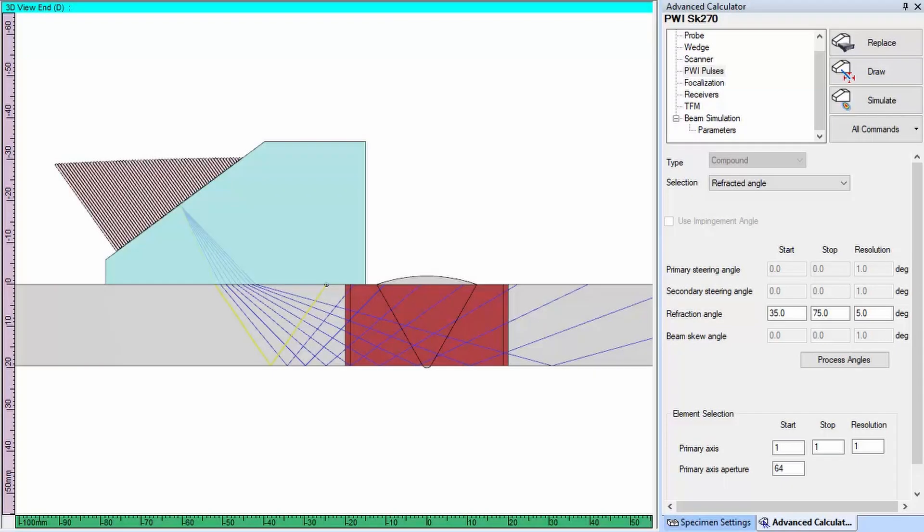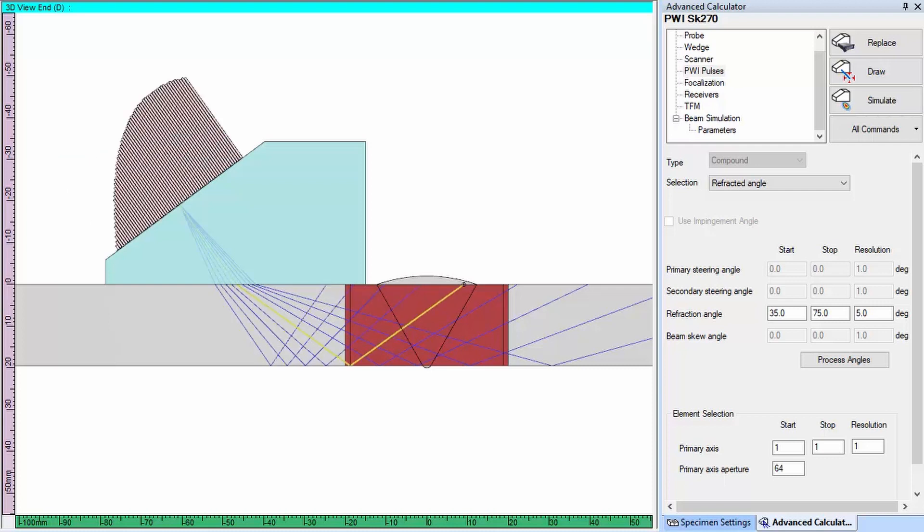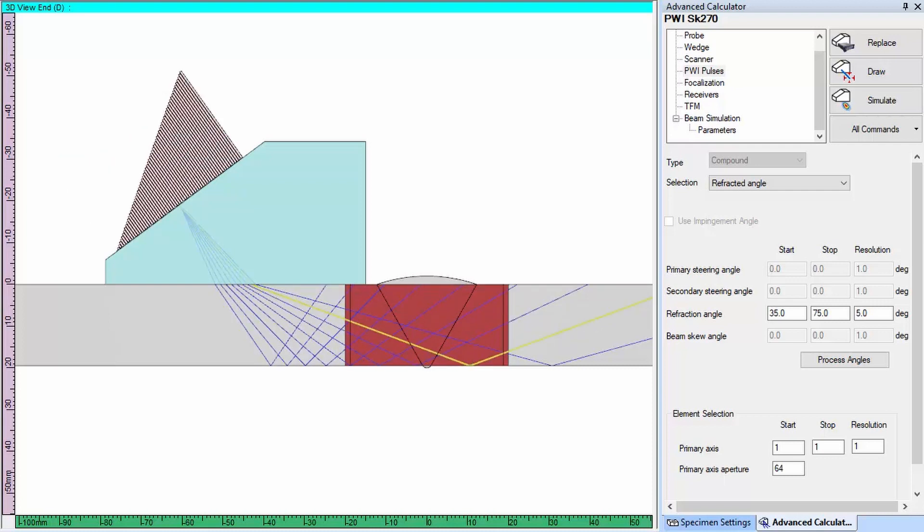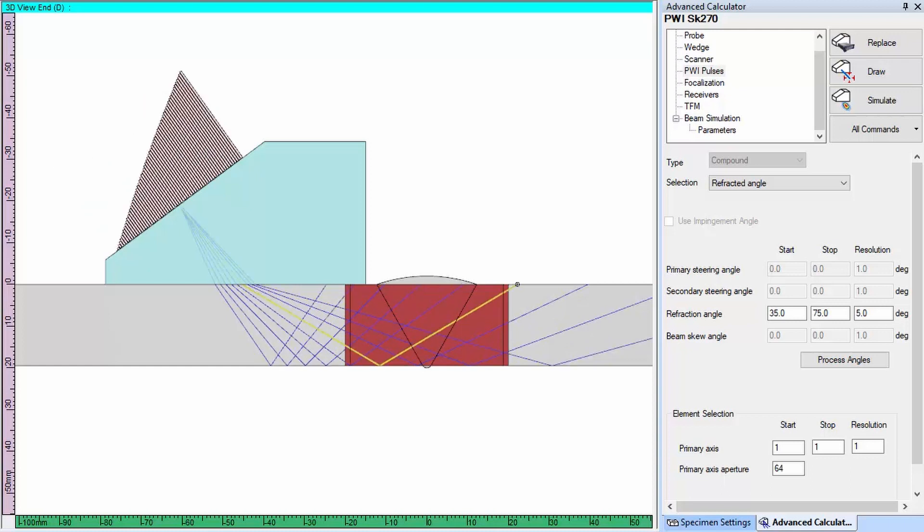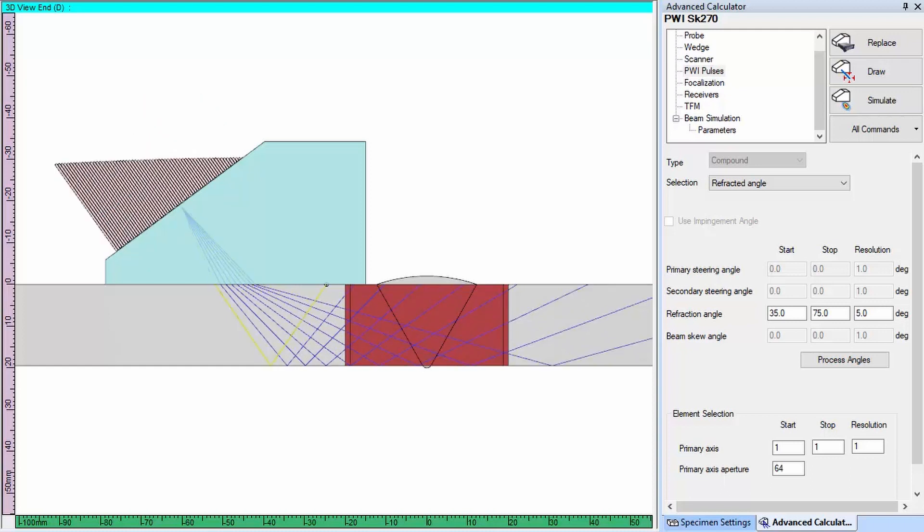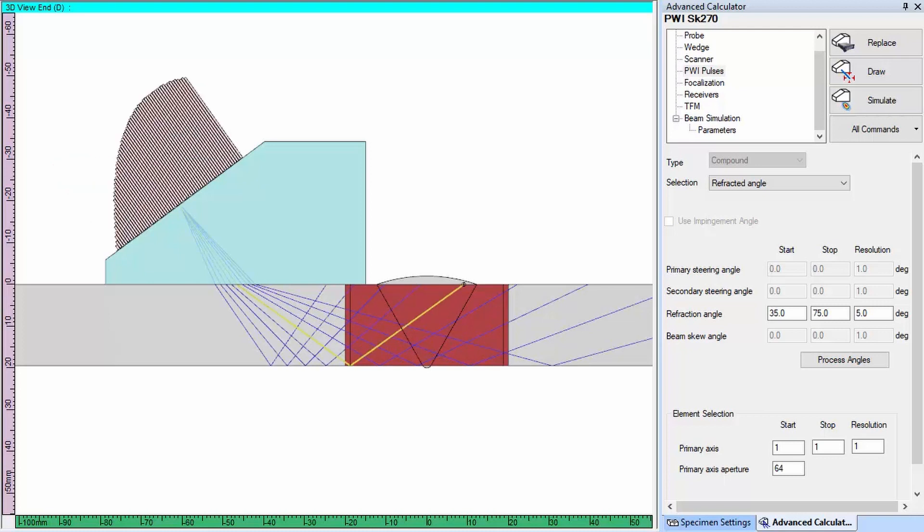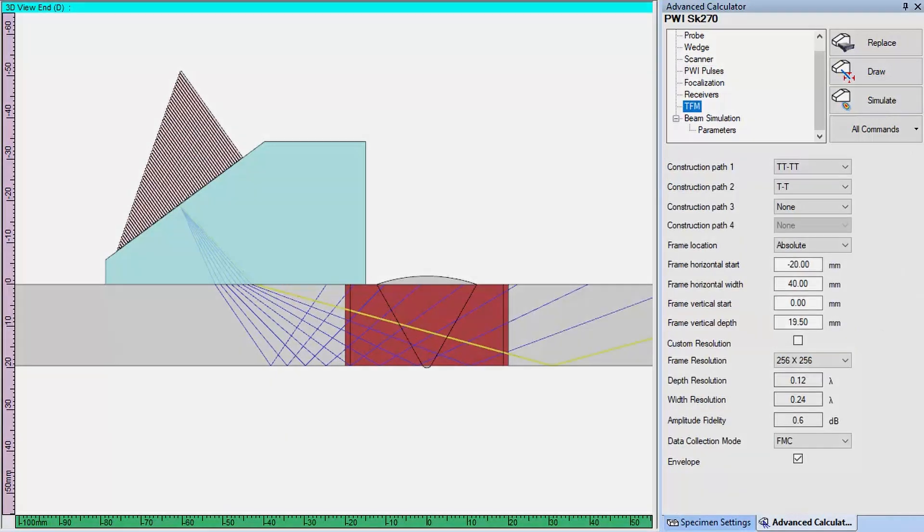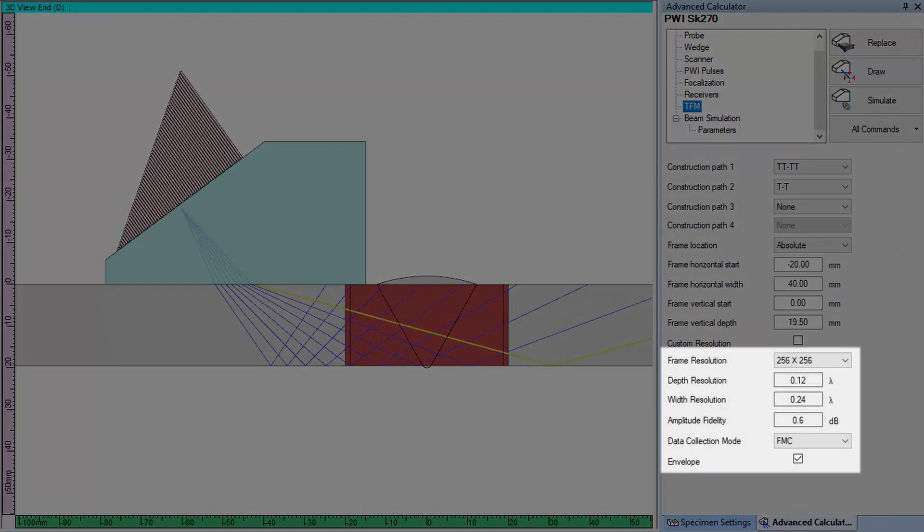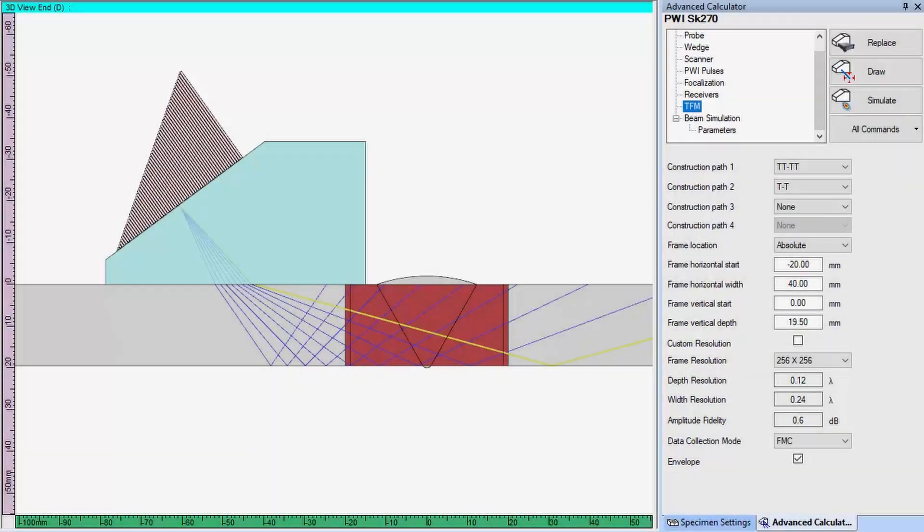For a typical weld inspection in full skip, we have selected an azimuthal sweep with the full aperture of the probe from 35 to 75 degrees shear wave with an increment of 5 degrees. In this case, we have a total of 9 laws. And on the receiving side, a 256 by 256 TFM frame with envelope provides a code-compliant amplitude fidelity of 0.6 dB.